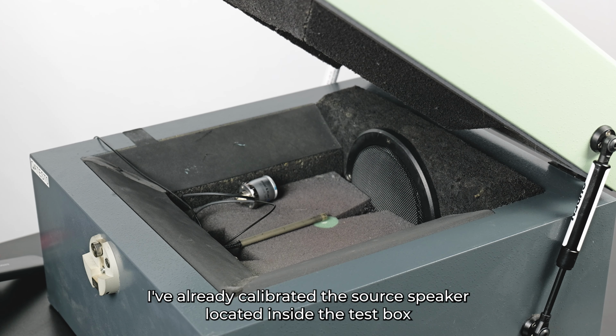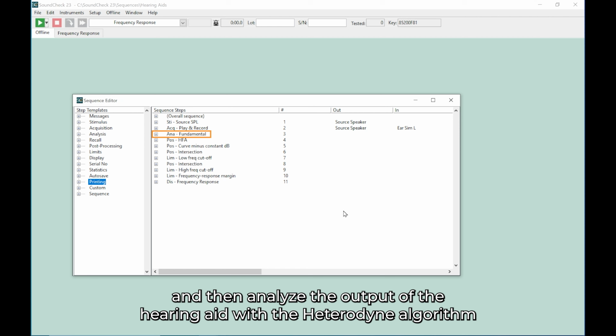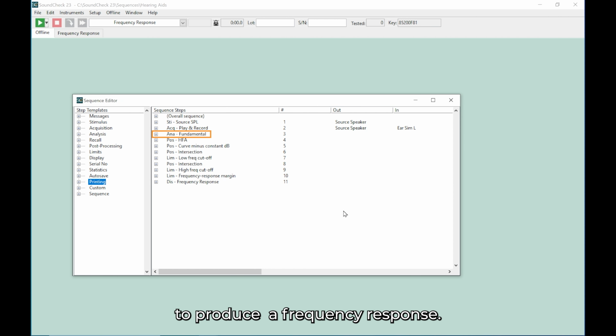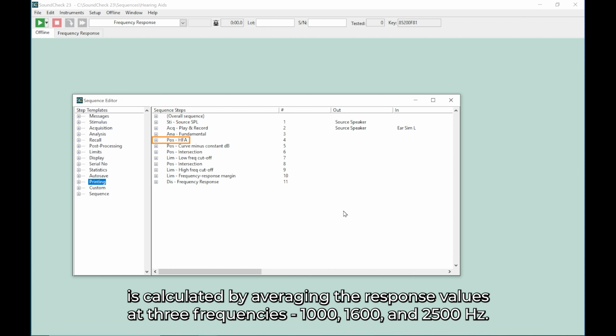Let's start with frequency response. The hearing aid should be set to its reference test gain. We'll play an equalized step sine sweep from 10 kHz to 100 Hz at a level of 60 dB SPL through the test box speaker, and then analyze the output of the hearing aid with a heterodyne algorithm to produce a frequency response. Next, the HFA, or high frequency average, is calculated by averaging the response values at 3 frequencies: 1000, 1600, and 2500 Hz.